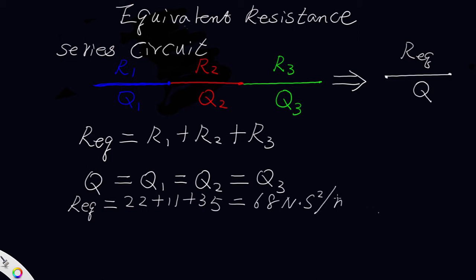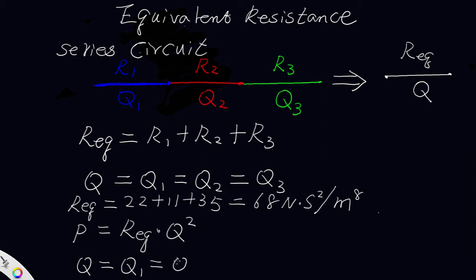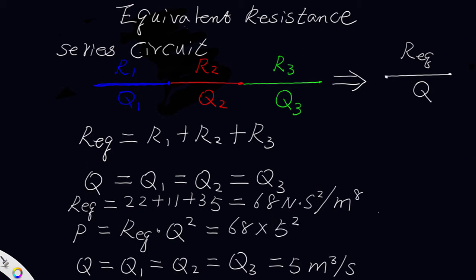Now we are asked to calculate the pressure drop in this set of series airways. The pressure drop equals R-equivalent times Q squared. Q equals Q1, and they are all the same: Q2 equals Q3 equals 5 cubic meters per second. Therefore, pressure drop equals 68 times 5 squared, which equals 1700 Pascal.